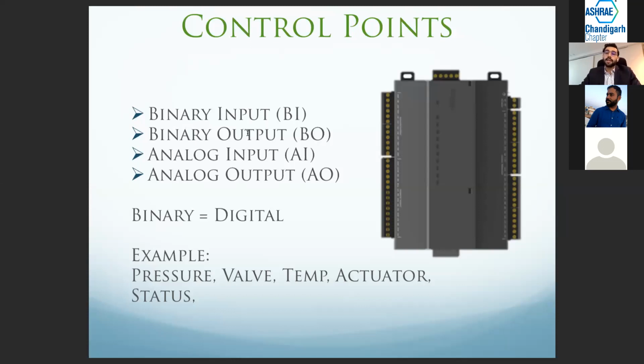You determine whether it's an input or an output by the direction of the signal. On the controller, the signal goes from the sensor to the controller, so the signal is an input, and hence a temperature signal is an analog input. Similar thing with pressure. On the other end, an analog output signal would be something like a modulating valve. The controller needs to tell the valve, hey, open up 50%, and that signal is sent from the controller to the valve, hence it is an output. So far, so good? I'm going to take silence as a yes.